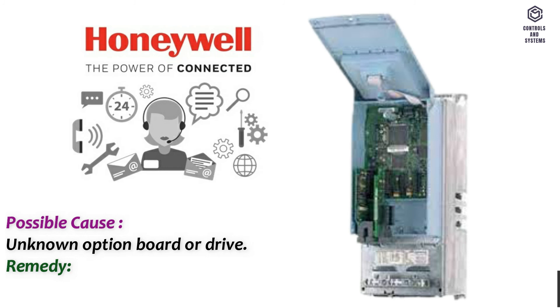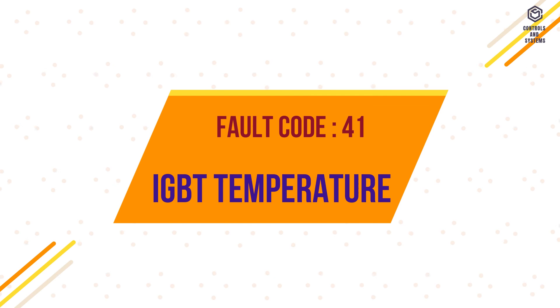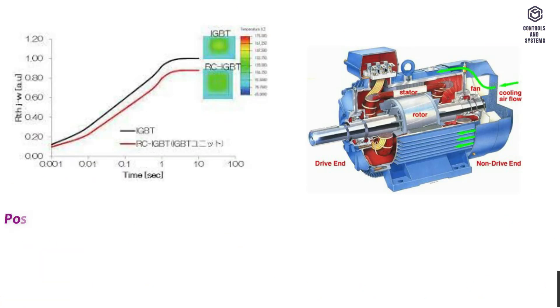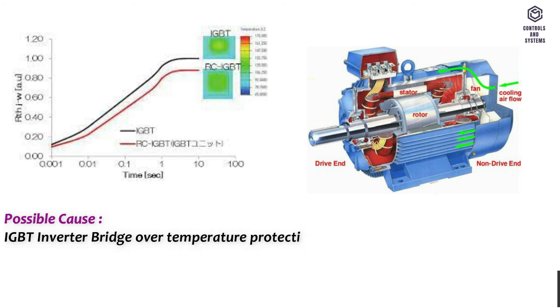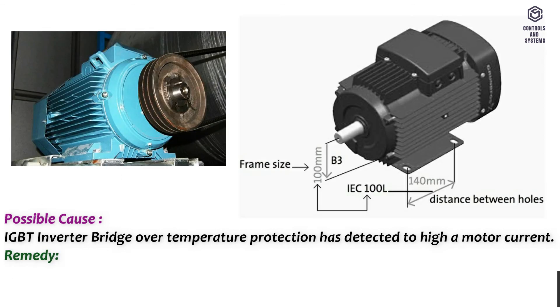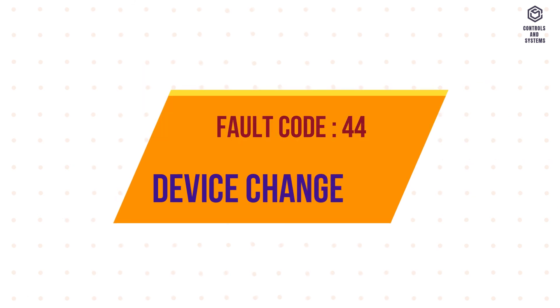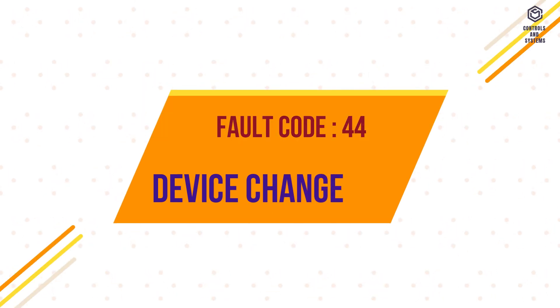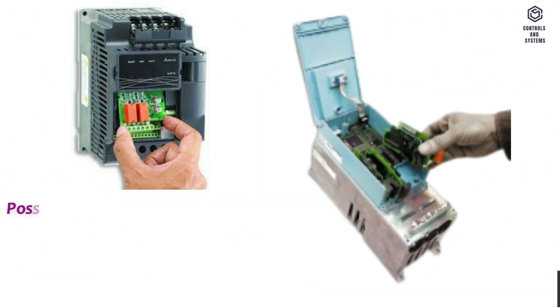Fault code 40 remedy: contact technical support. Fault code 41 – IGBT temperature. Possible cause: IGBT inverter bridge over-temperature protection has detected too high a motor current. Remedy: check loading, check motor size.